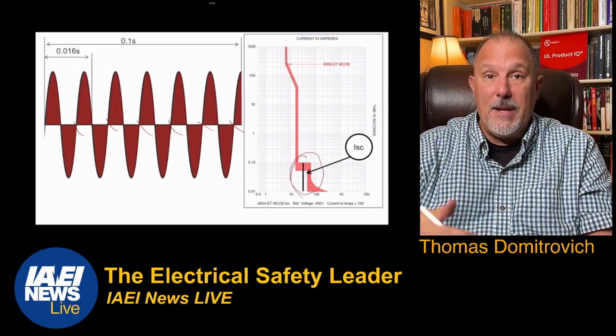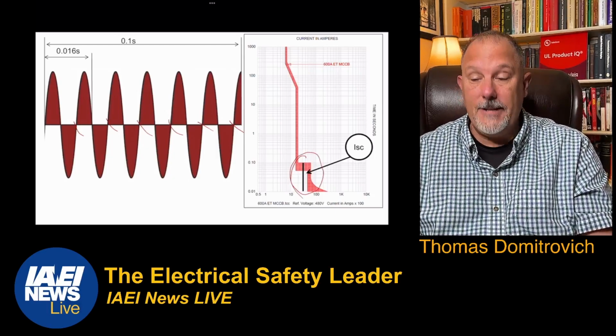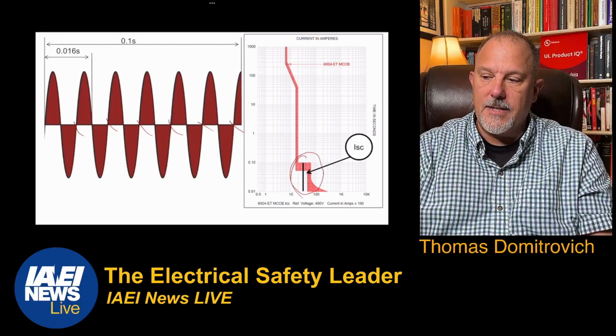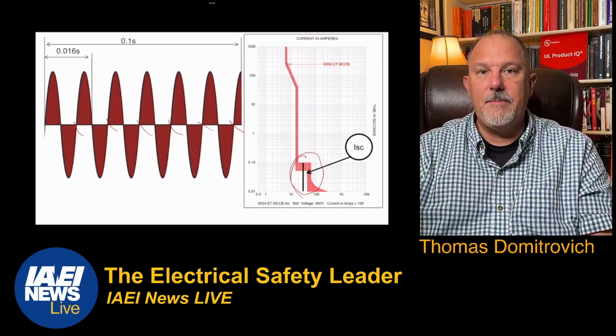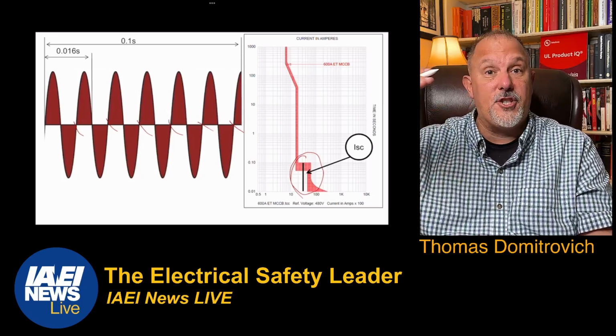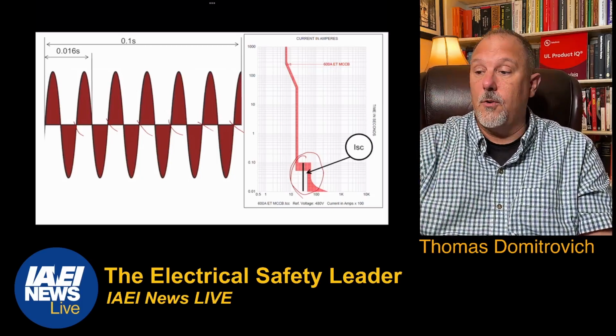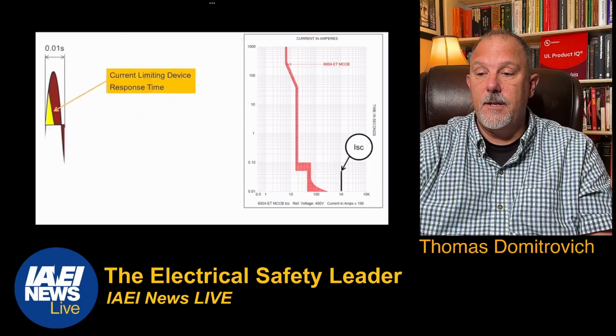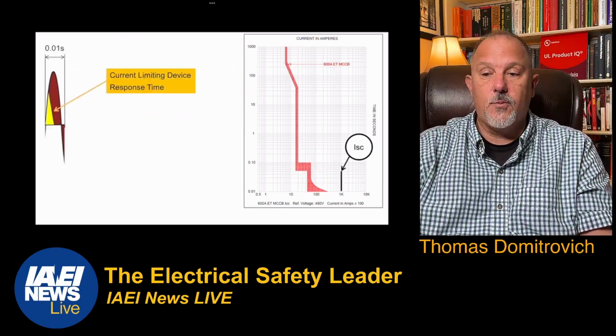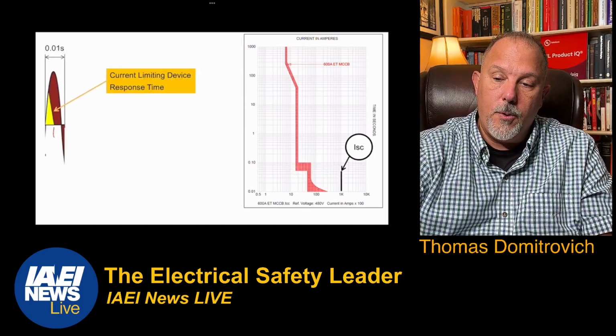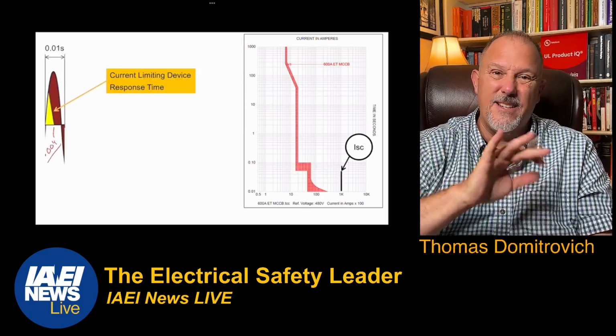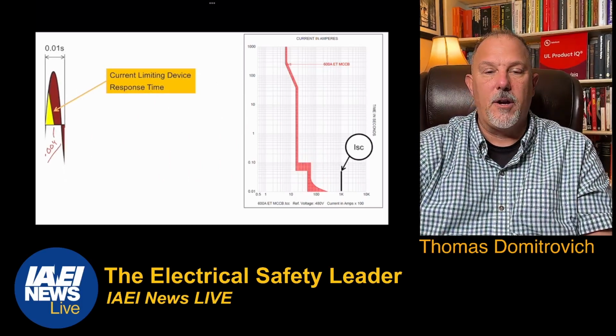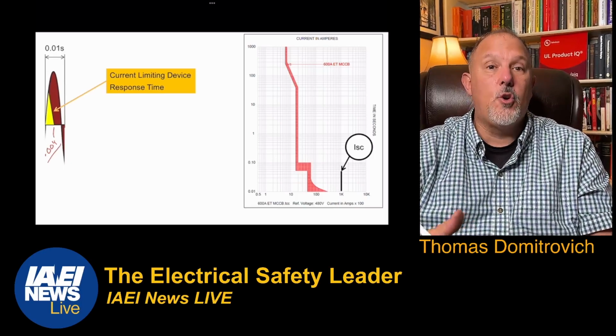And think about what that means to incident energy, right? So that's the clearing time for a short time delay for this breaker. It can be adjusted higher or lower in some cases. A current limiting device will let 0.004 seconds through on average, somewhere in that ballpark, a half, 1/4 of a cycle.